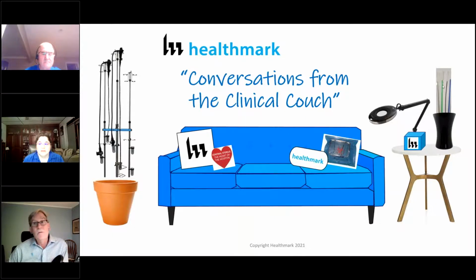And AAMI's not the only one speaking to this. So this is not in isolation where AAMI's out on an island. Just last month, the multi-society guideline was updated again, and they actually reference point of use treatment as well. So it's going to be used more and more as time goes on. And they're also reinforcing active filtered forced air drying as well. I mean, clinical investigations and research have both shown the reality of residual moisture and the problems that residual moisture can cause.